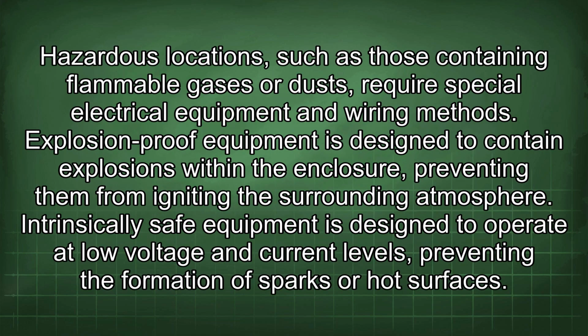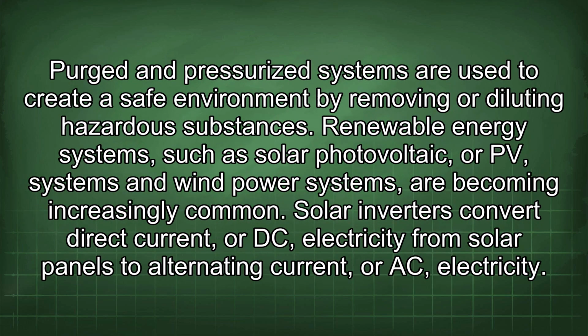Hazardous locations, such as those containing flammable gases or dust, require special electrical equipment and wiring methods. Explosion-proof equipment is designed to contain explosions within the enclosure, preventing them from igniting the surrounding atmosphere. Intrinsically safe equipment is designed to operate at low voltage and current levels, preventing the formation of sparks or hot surfaces. Purged and pressurized systems are used to create a safe environment by removing or diluting hazardous substances.